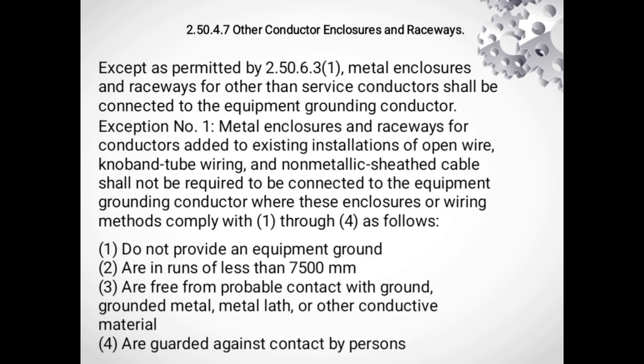Moving to section 2.50.4.7, we address enclosures and raceway for conductors other than service conductors. Here the requirement shifts slightly. Metal enclosure and raceway containing these conductors must be connected to the equipment grounding conductor, or EGC. The EGC provides a path for fault current back to the source, tripping the overcurrent device. This is crucial for protecting personnel and equipment from ground faults in branch circuits and feeders.